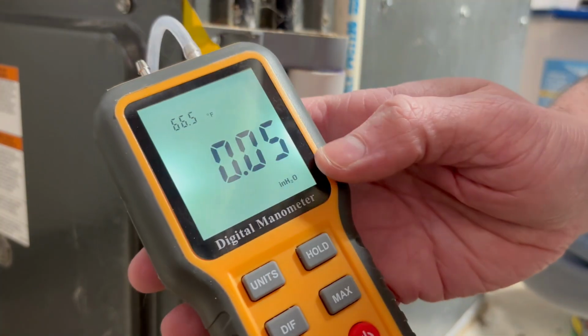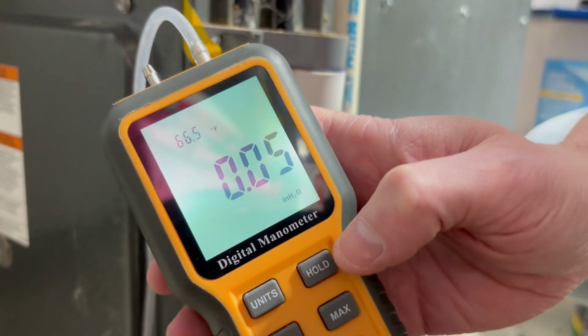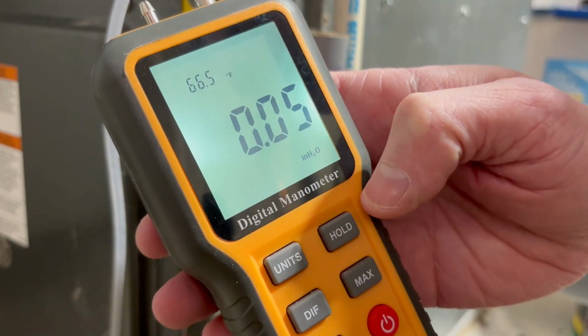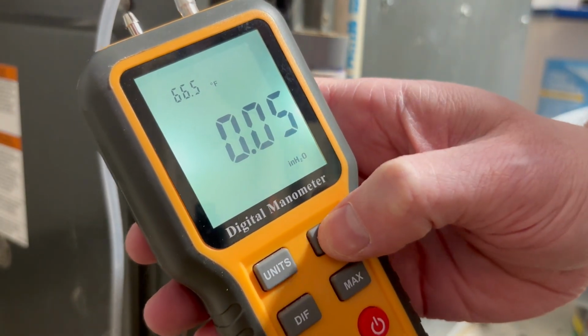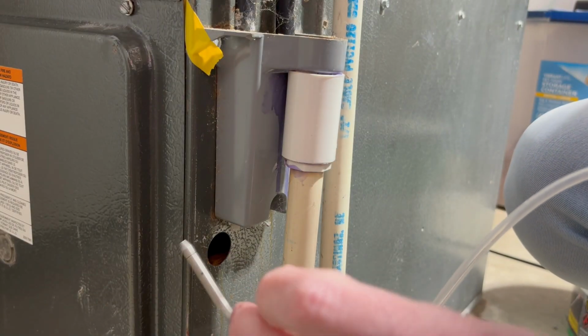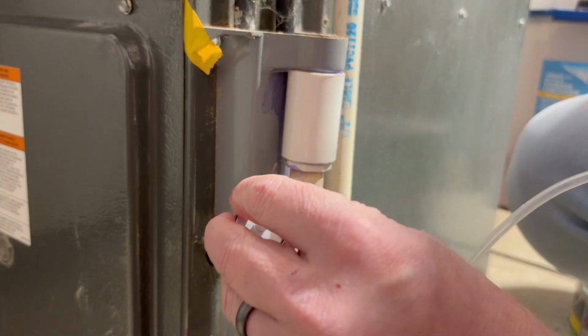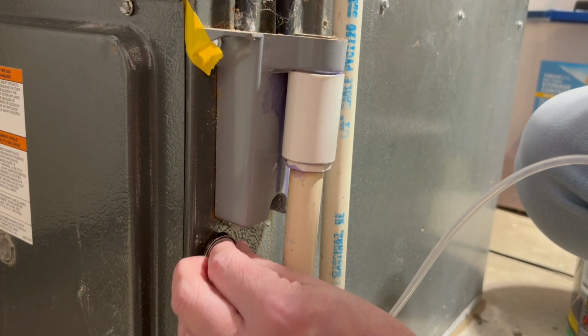And so when using a manometer, it's important that we zero out the reading before we start measuring. And then what I can do is just take my static probe and place it here inside the test port.